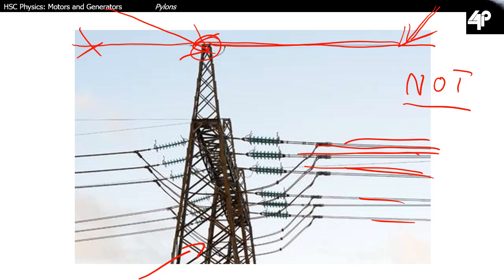Because it's not insulated, the lightning is just simply going to travel to the ground using the shortest route, which is usually directly through the pylon itself, and this is usually straight through the center of the pylon, through the metal of the structure. And in doing this, it avoids the horizontal sections of the tower here where the lines are typically connected to. So you're going to be traveling through like so, straight to the ground.